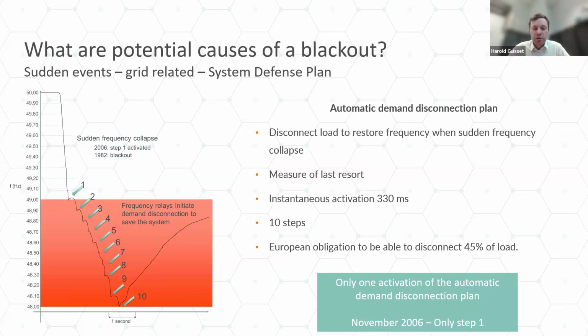It's all over Belgium, those 10 different slices. Basically, if there's a sudden frequency collapse, then at a certain level, which is 49 hertz, the first slice would be disconnected. You should know that a lot of defense mechanisms are also in place between the 50 and the 49 hertz. So a lot of other stuff would happen before we would activate the automatic load shedding. The automatic load shedding is really a measure of last resort, after all other defense systems have failed.